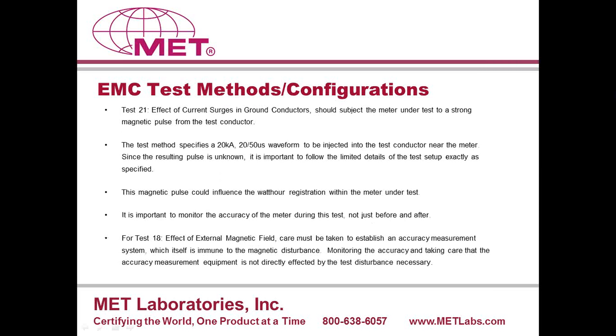Now let's look at test number 21 and test number 18, that is the effect of current surges in ground conductors and the effect of external magnetic field. As we just briefly mentioned, test number 21 subjects the meters to very strong magnetic impulses, and it simulates the effect of an indirect lightning discharge that occurs in the vicinity of a ground rod. Now the wave shape is typically a bi-exponential current impulse.